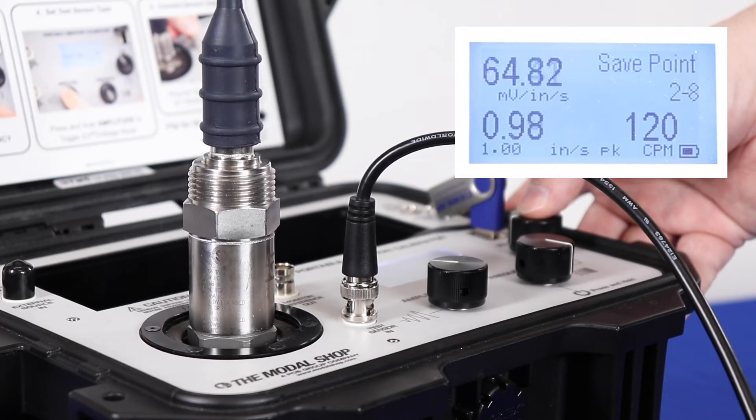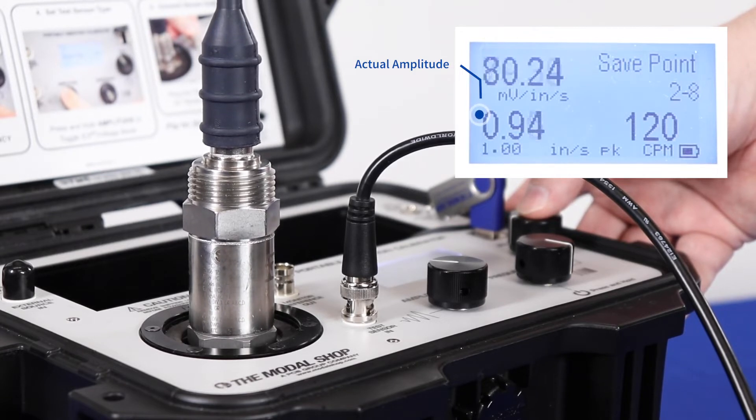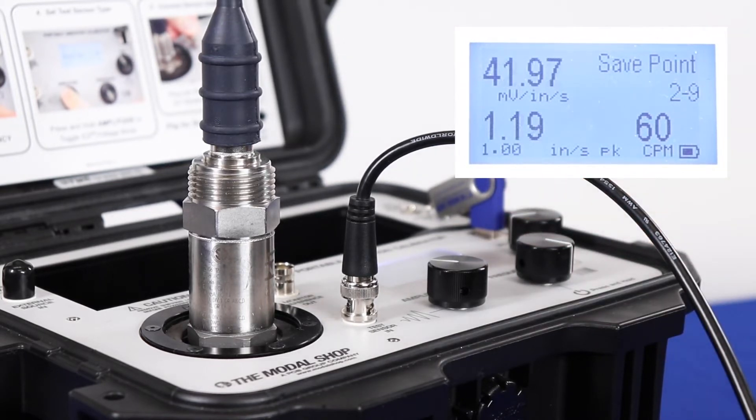At 120 cycles per minute, we need to wait longer for the shaker to settle on the target amplitude of 1 inch per second. The target amplitude is the smaller number at the bottom of the screen; the actual amplitude is the larger number located directly above, as measured by the device's reference accelerometer. At 120 cycles per minute, the output of our sensor under test is 80 millivolts per inch per second, which still passes calibration. The last test point of 60 cycles per minute is below the sensor's maximum low frequency range.